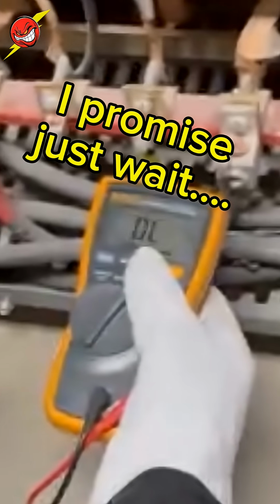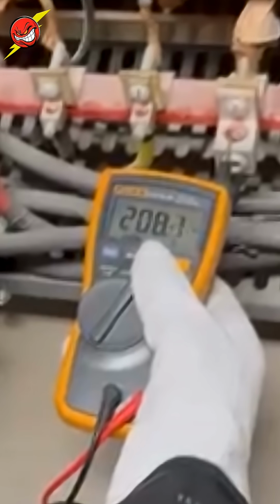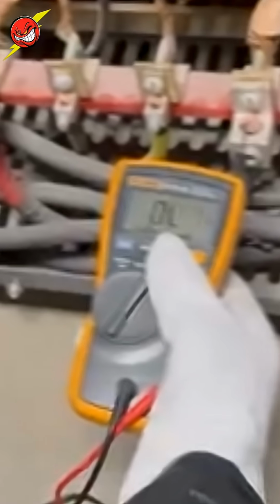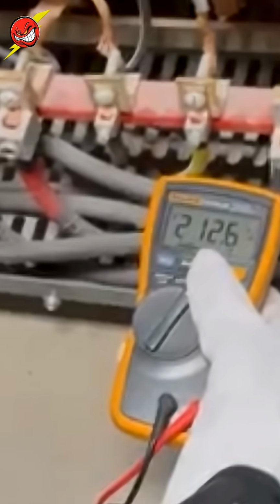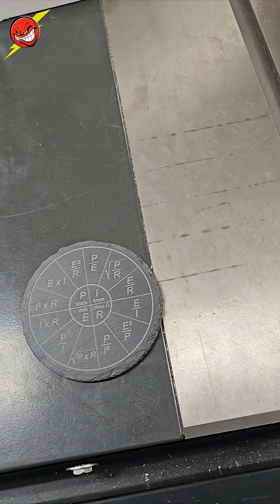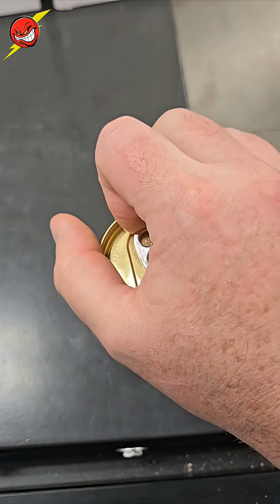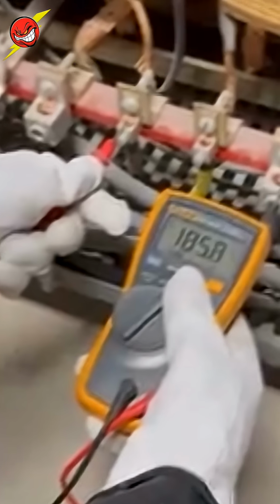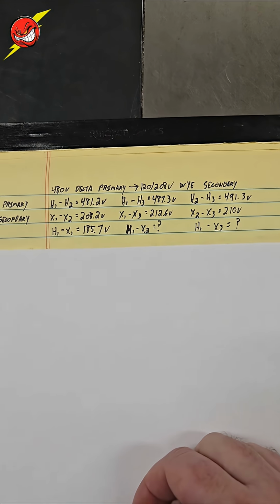And we're going to go X1 to X2, 208, X1 to X3, 212, X2 to X3, 210. Have you guys ever wondered what the voltage is from an H terminal to an X terminal? Oh, I've done way more than wonder. So check this out. We're going to go from H1 to X1. We're only reading 185.